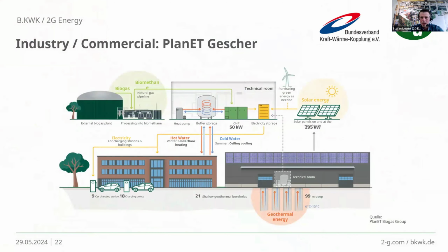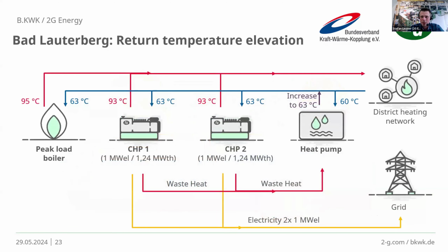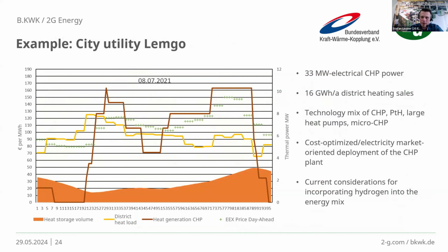So just a few sheets for first ideas of how this could look. Here you have just a small industry combination, a 50 kW CHP plant with geothermal solutions, with PV solutions, with biomethane use. You have another one, where I was mentioning the waste energy or waste heat of the CHP. That's an example by a German Stadtwerk in Bad Lauterberg. They're doing exactly that. They use the waste heat and have a heat pump in the backflow, and by feeding the heat pump with the waste heat, the backflow can be increased from 60 to 63 degrees Celsius for the CHPs, so that in the very end the peak load boiler is not used, or at least used less, with this combination.